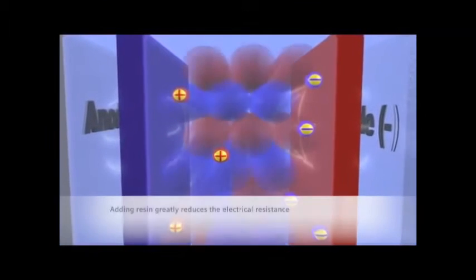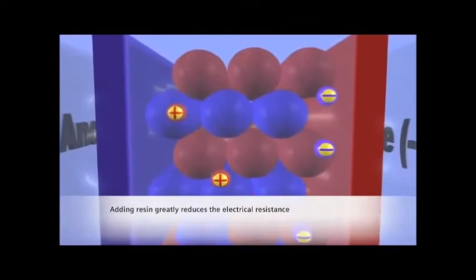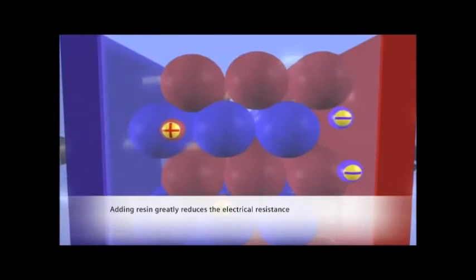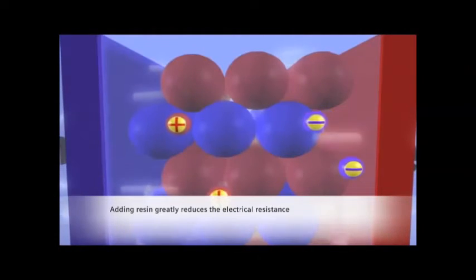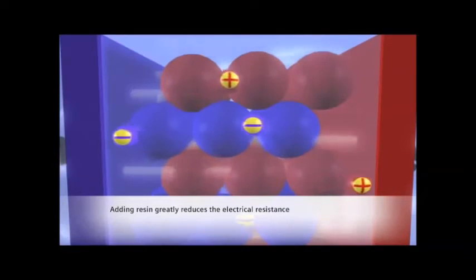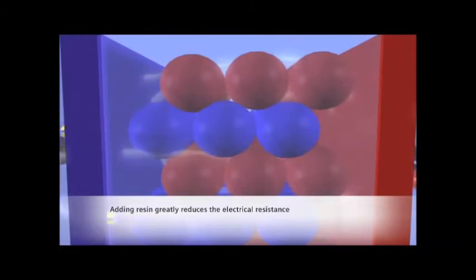IonPure's CEDI technology solves this problem by sandwiching a mixture of cation and anion-selective resins between the two membranes. The large surface area offered by the resin beads effectively eliminates the ion diffusion resistance and allows the ions to move freely, even in ultra-pure water solution.